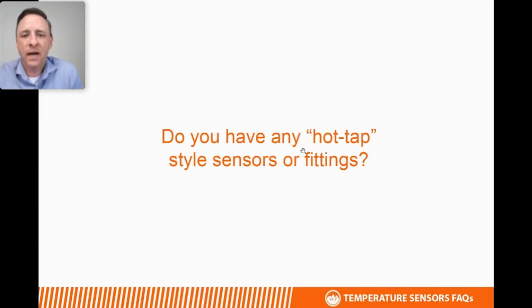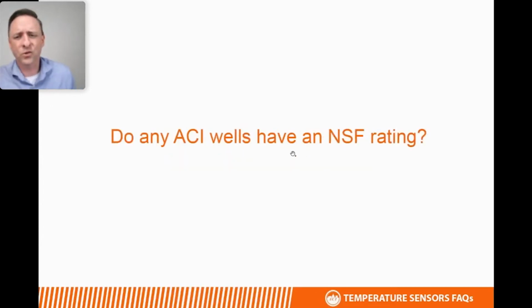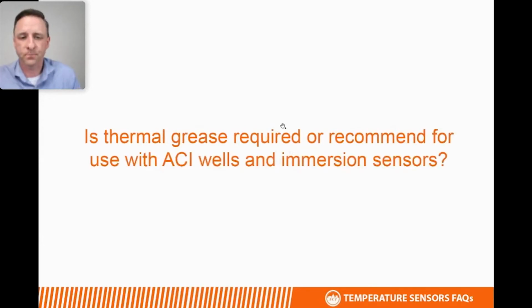Do we have any hot tap style sensors or fittings or wells? No. From my understanding, that's a type of well that allows it to be installed without having to drain the system. It's got a valve built into it. And we've never seen any of these that are completely leak free, so we don't offer anything like that. Our wells do not have an NSF rating. That's a rating commonly used for food service applications. However, I have seen some of our 316 stainless wells be approved in these types of applications, but we do not have a specific NSF rating on any of our thermowells.